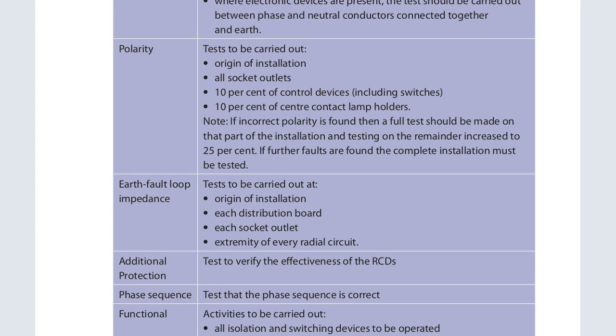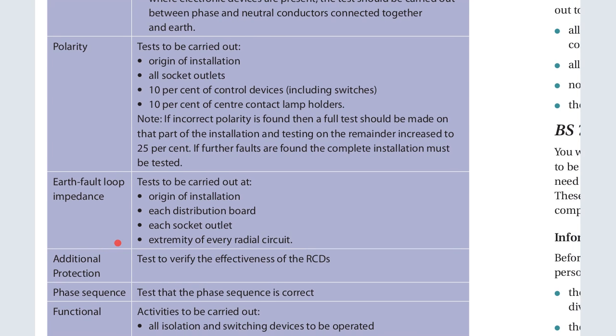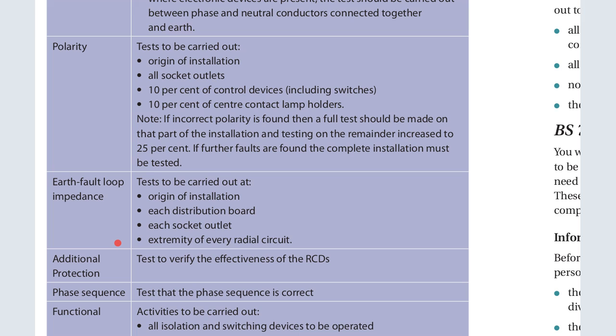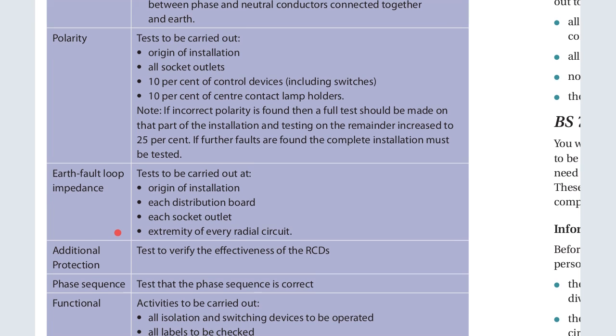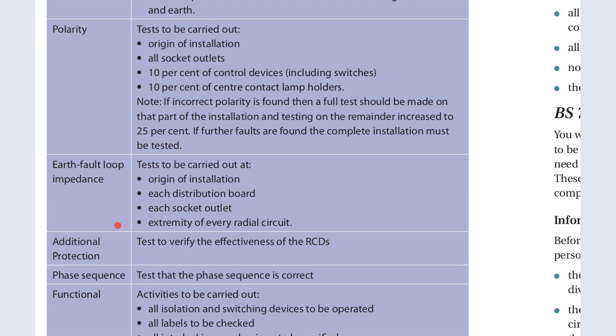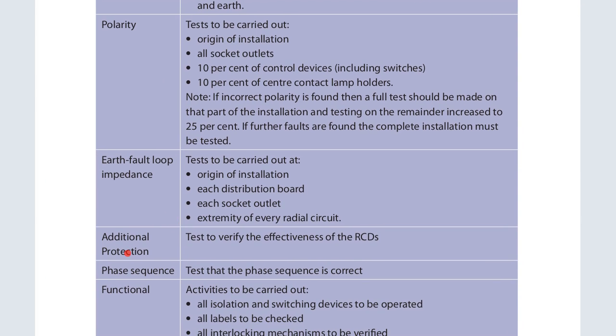We said that the polarity test is carried out on the origin of installation, also on all sockets, on 10 percent of control devices, including the switches, and 10 percent of the lamp holders. Note that if incorrect polarity is found, then a full test should be made on that part of the installation, and testing on the remainder is increased to 25 percent. So if further faults are found, then the complete installation must be tested.